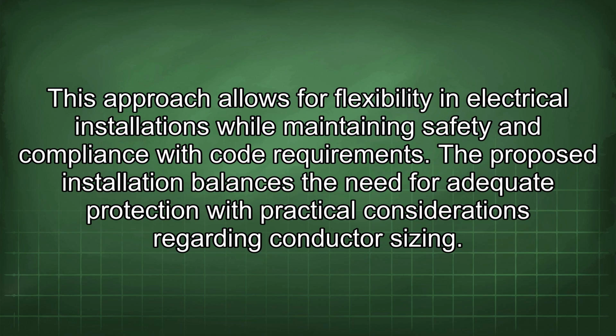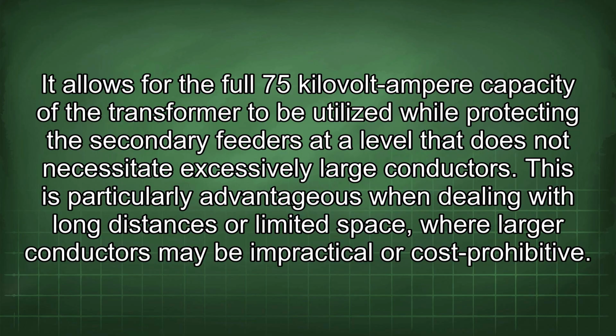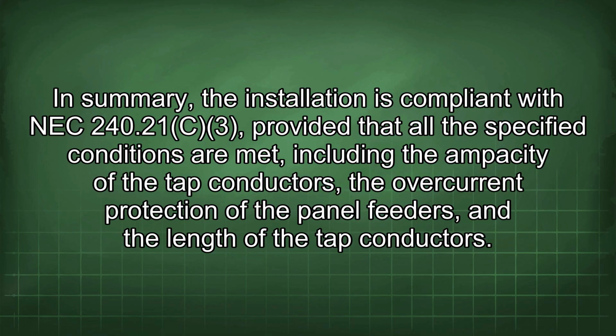The proposed installation balances the need for adequate protection with practical considerations regarding conductor sizing. It allows for the full 75 kVA capacity of the transformer to be utilized while protecting the secondary feeders at a level that does not necessitate excessively large conductors. This is particularly advantageous when dealing with long distances or limited space, where larger conductors may be impractical or cost prohibitive.